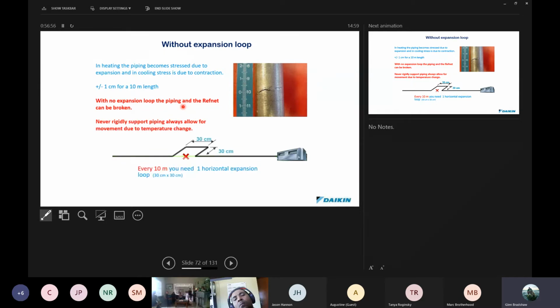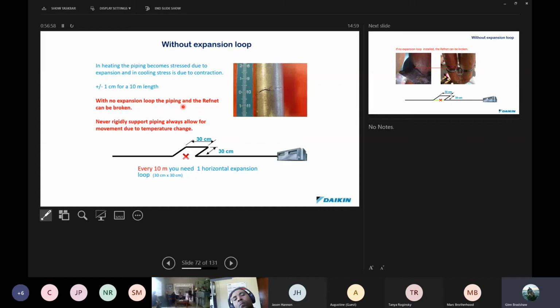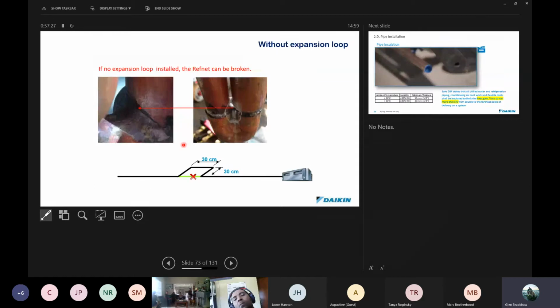Never rigidly support piping. Always allow for movement due to temperature change, so it's not a good idea to clamp piping down. Allow for some movement. The expansion loop we're talking about, if required, is a 30 centimeter by 30 centimeter horizontal loop, and in systems you may have to put this in every 10 meters, if provision for movement has not been allowed.